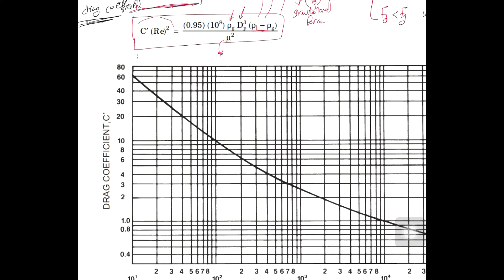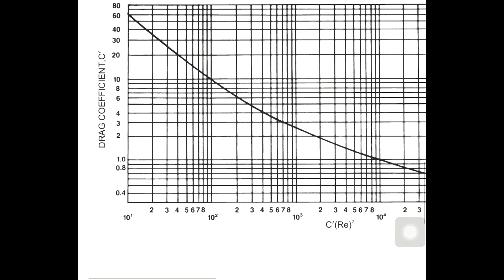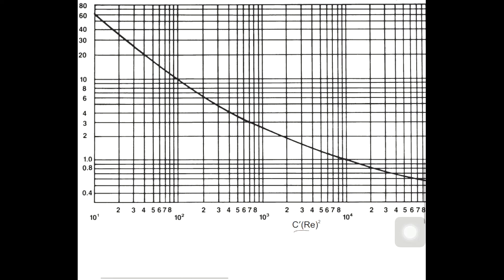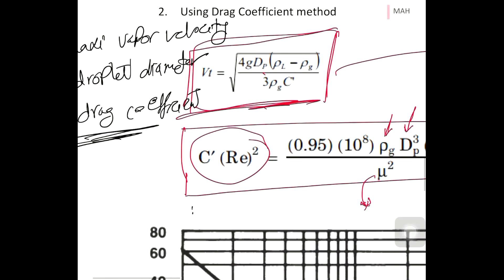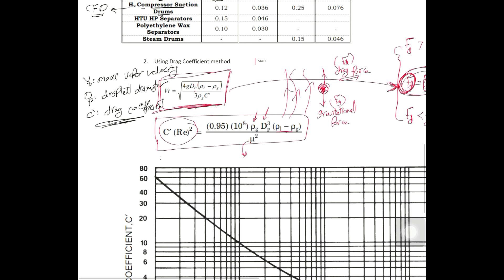We can calculate the x-axis value, then go up to the intersection with the curve and read off the drag coefficient — for example, C' = 1. We then substitute into the equation. The importance of this approach is that it helps you calculate the maximum droplet diameter that will be carried away with the vapor.